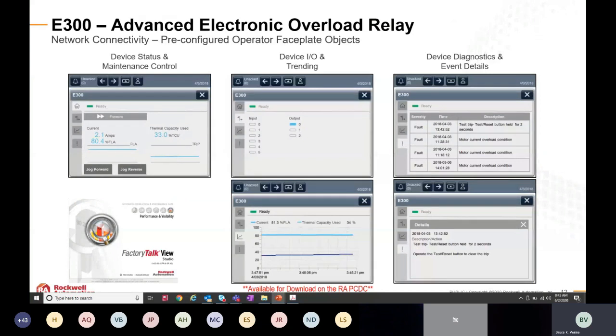If you're familiar with HMIs, the E300 also has its own dedicated set of pre-configured faceplate objects that are available from ab.com. These faceplate objects are specifically designed only for the E300. What's nice about it is if you have an operator display maybe at the machine or in a control room somewhere and you're looking to mimic what the E300 is doing, this is a good tool to use if you're familiar with the software FactoryTalk View. Again, it gives you access to device status and maintenance control, the different I/O points. You can even look at the trending of the full load amps that the E300 is monitoring, the voltage and the power and everything. And then some of those diagnostics that I mentioned, if there's a trip event, you can actually see the different things there for that too.